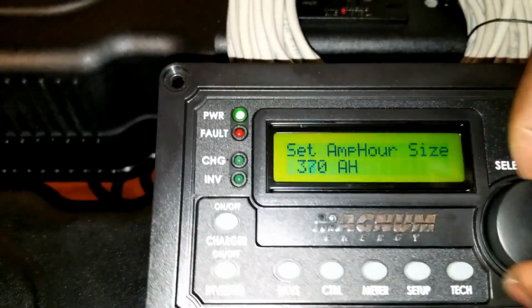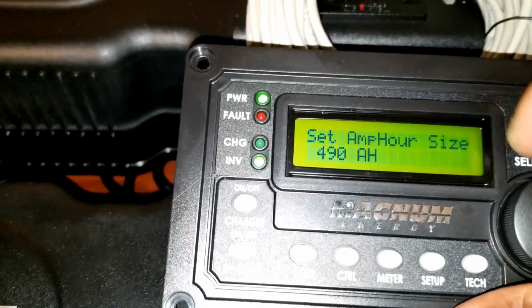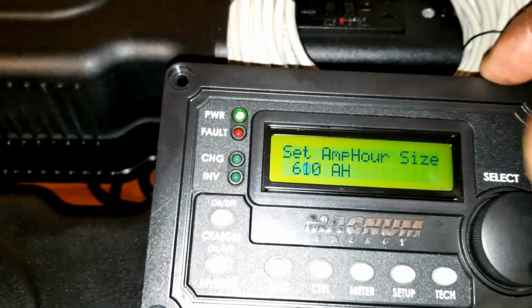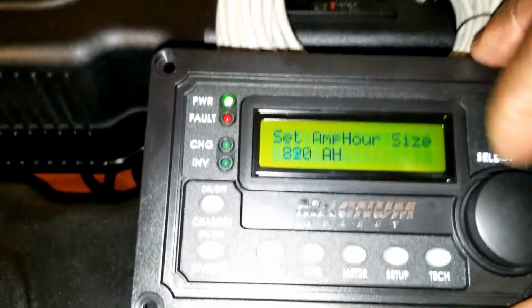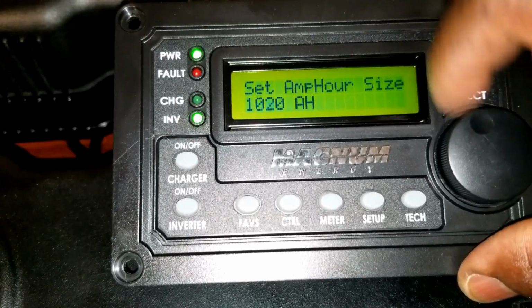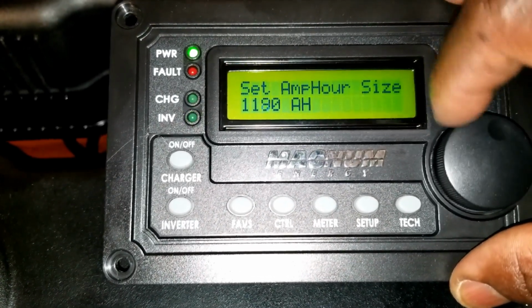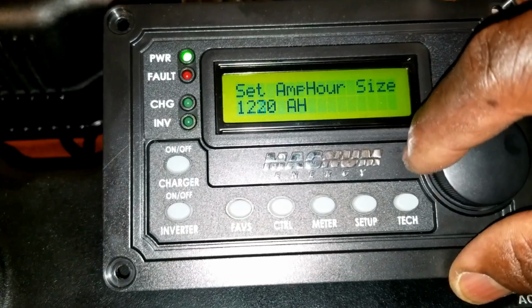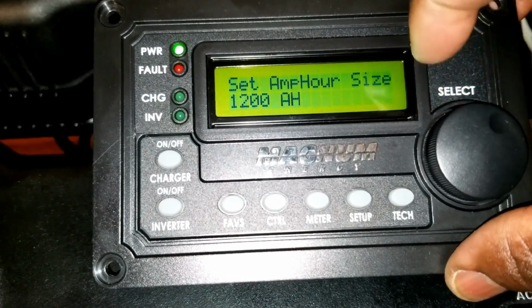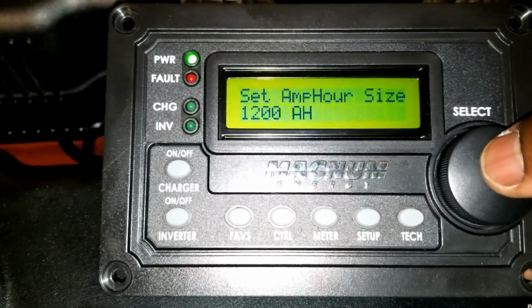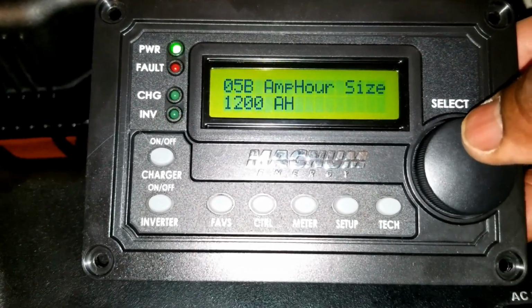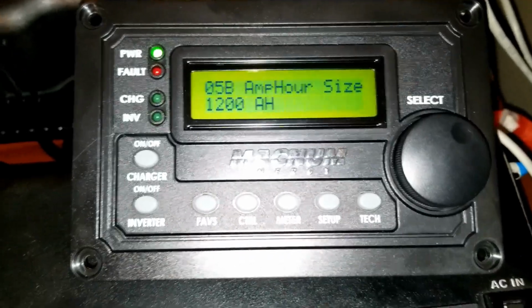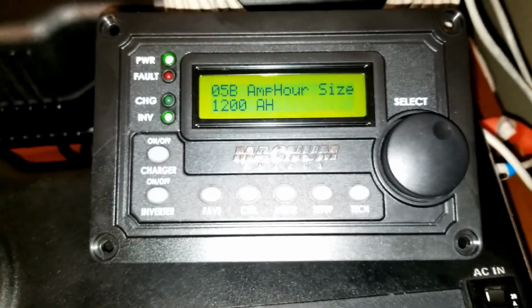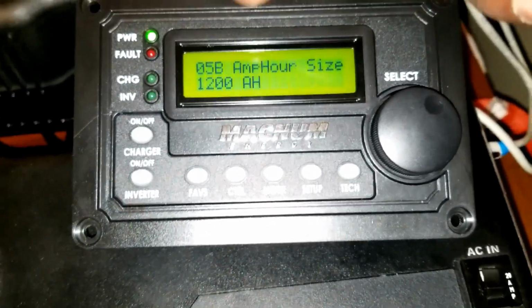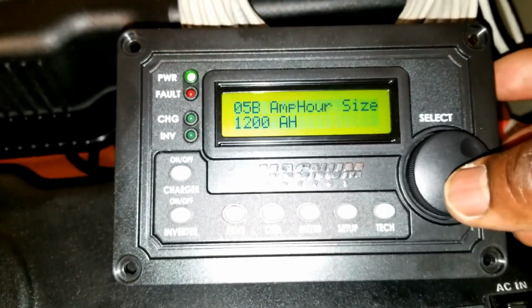It's gonna be long going. You want to keep doing this till we get to the 1200, so the machine will know exactly what's the total amp hours of the battery bank, so that we're able to charge it. So 1200, there you go, 1200 amp hours. Push enter, it's programmed. Now it's gonna recognize that it's 1200 amp hours, this is the capacity of the battery. So we had to charge it to make sure it reached the 1200 amp hours.